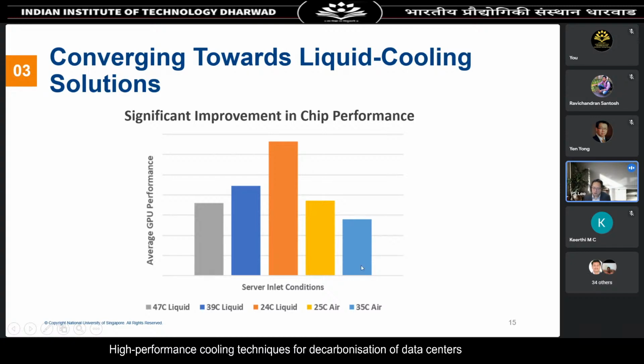So if you were to increase the inlet temperature for air cooling from 25 degrees to 35 degrees, you see there's actually a penalty in terms of GPU performance, because now the GPU performance is lower by about, for example, 15-20%. But if you were to switch from 25 degrees C air cooling to 24 degrees liquid cooling, you notice a big improvement in GPU performance, by as much as 80%.